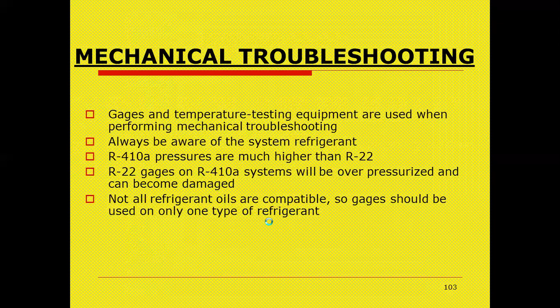R410A pressures are much higher than that of R22 refrigerant. R22 gauges and temperature testing equipment used on 410A systems will be over-pressurized and can be damaged. Not all refrigerant oils are compatible, so gauges should be used only for one type of refrigerant.